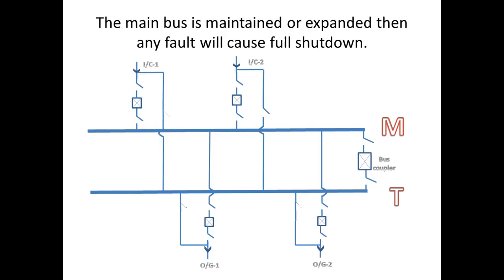Now we go to the disadvantages. First, when the bus is in maintenance, by transferring all the circuits to the transfer bus, protection depends upon the remote backup relay and breaker for removing faults. During this condition, a line fault on any circuit could shut down the entire substation.